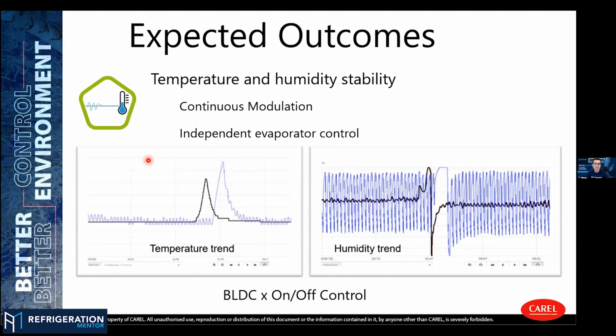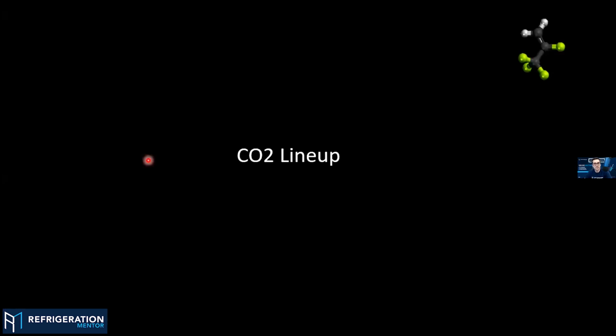Yeah, and I've seen that before too. These systems have very low charge, but you just want to get that pressure up. There's always a little potential, but you open it up, the pressure goes up, it starts up, and then it just runs. But that's a good thing. That's something you should check. The person who asks, like when you're in the field, these are things you should check, especially if you haven't worked on a piece of equipment. This is all about testing and measuring your system, and this is how you learn. So if you ever come up to the system, even though it's going to tell you all the pressures and temperatures on the drive or on the controller, you need to verify that the temperature probe is reading accurately. As technicians out there, you need to verify that stuff. So important. Thank you for the question. It was great. Oh, perfect.